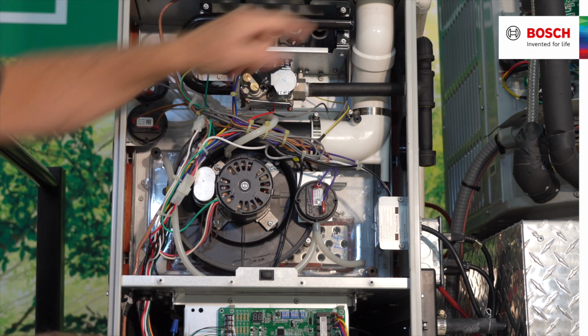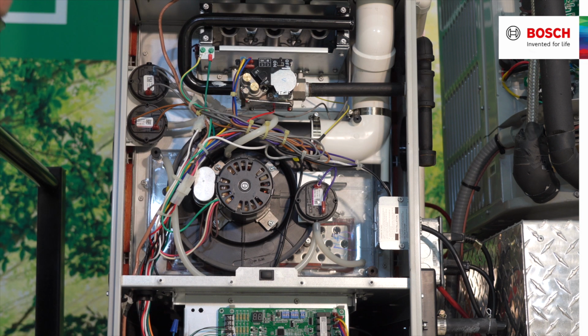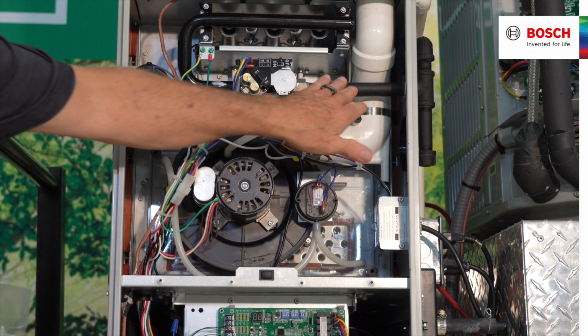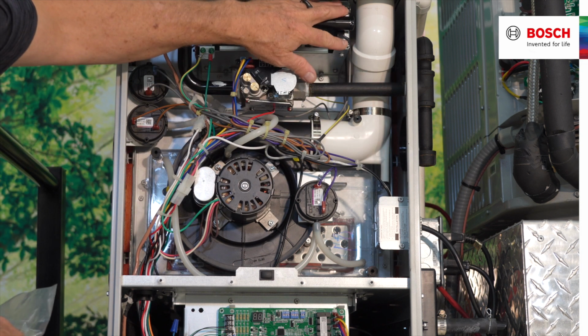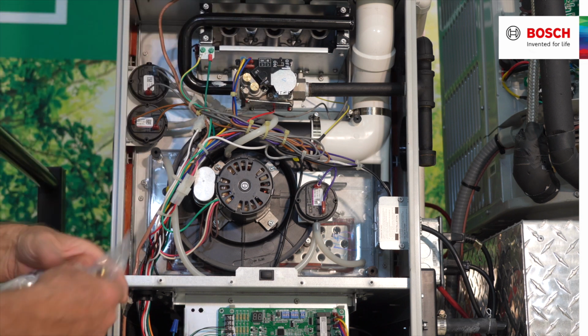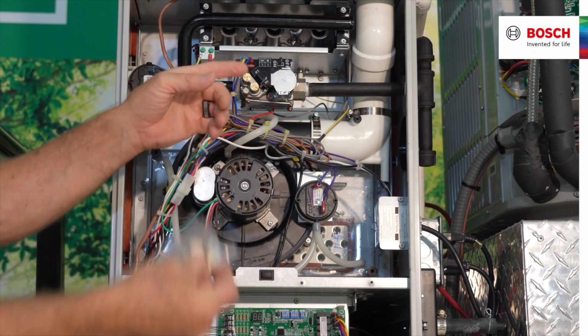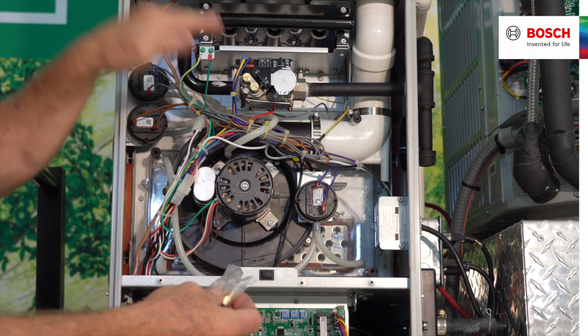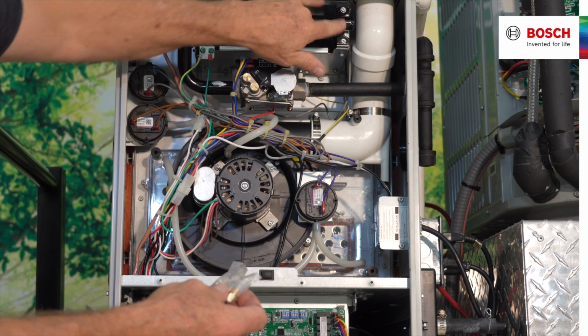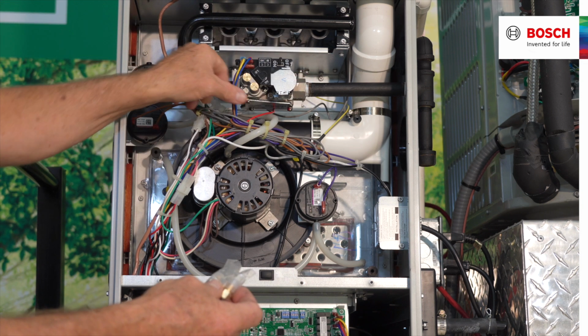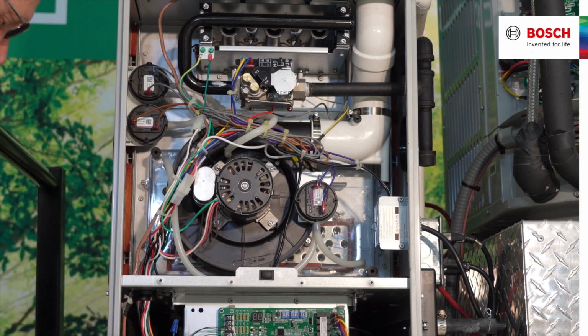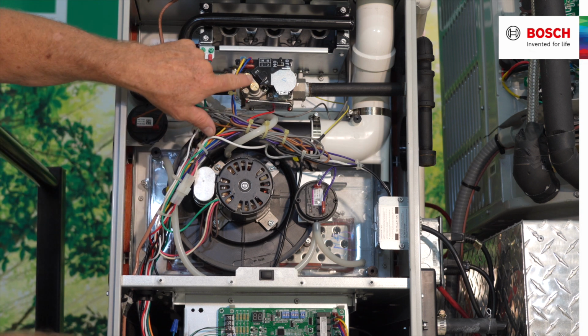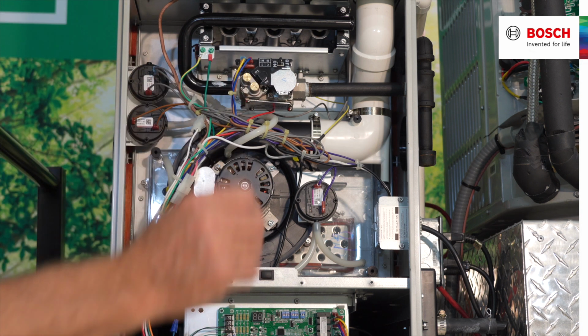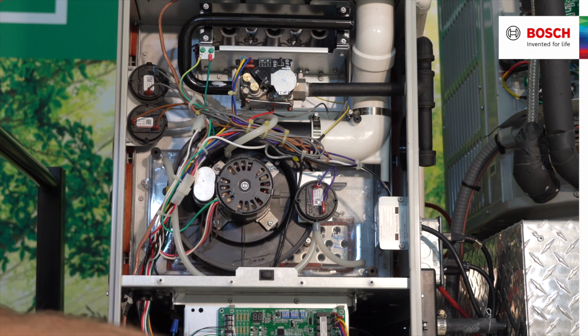Here are the burners. If I'm going to replace the burners and change the orifices, you're going to, of course, take the gas pipe off, remove these 4 screws, take the pipes out, change the orifices, make sure that they're not cross-threaded, make sure that they're straight, insert the burner back in, replace the 4 screws, replace the gas valve wires, and then, of course, the gas piping. I want you to know that we have a low fire and a high fire spring so that we can replace those when we're converting from the natural gas type setting to propane.